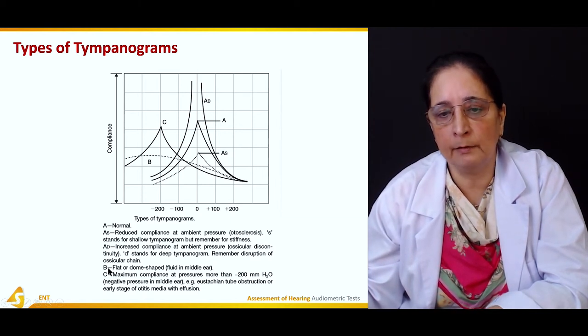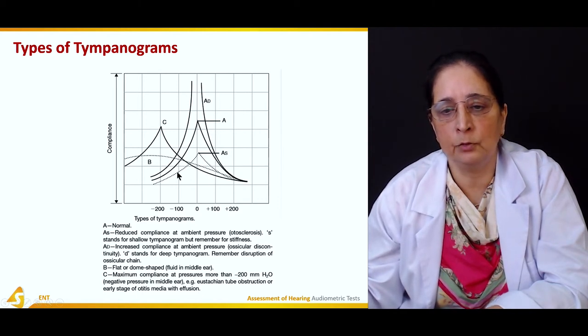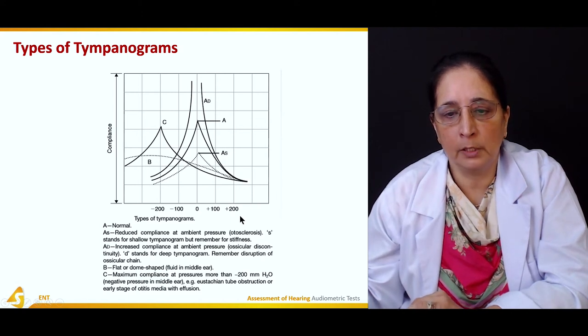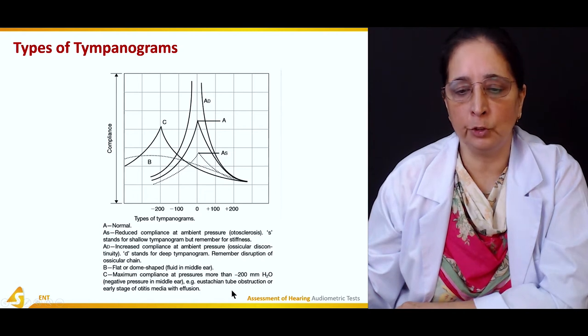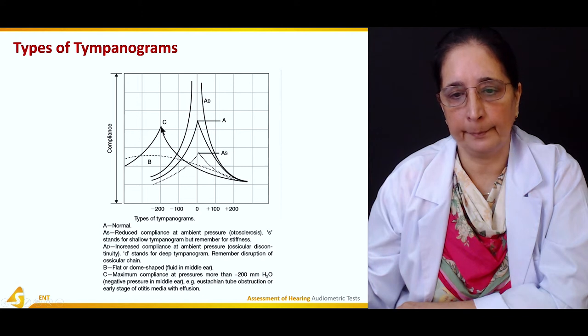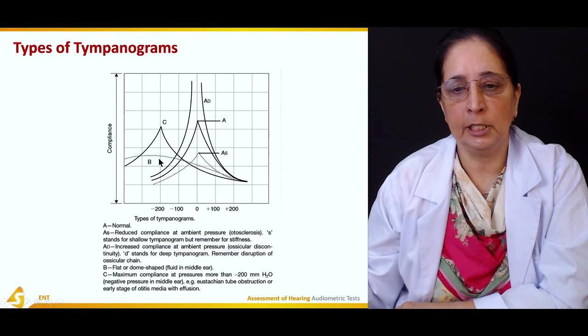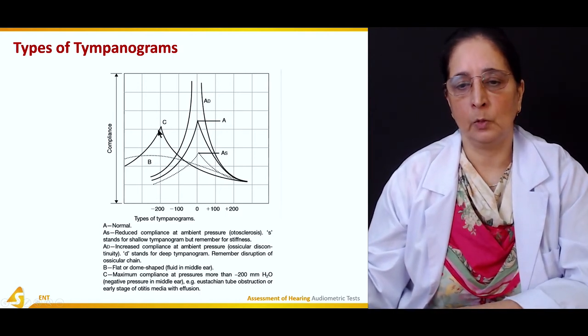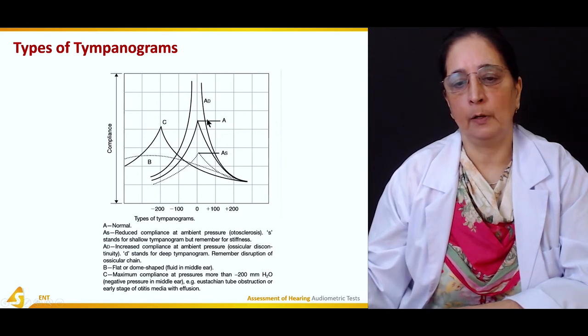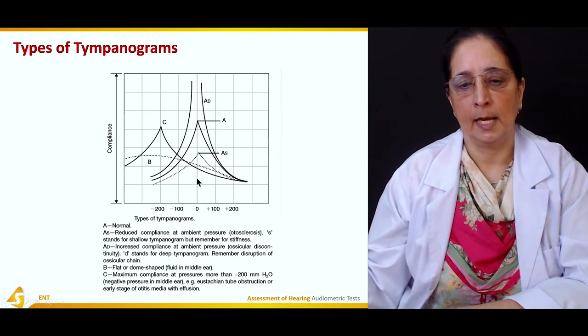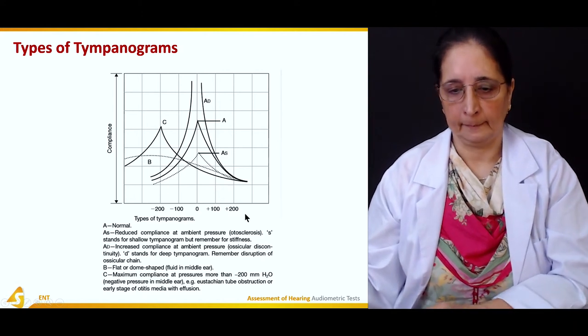Type B is a flat or dome-shaped tympanogram, mainly due to fluid in the middle ear. Type C shows maximum compliance at a negative pressure greater than minus 200 millimeters of water, mainly due to Eustachian tube obstruction.